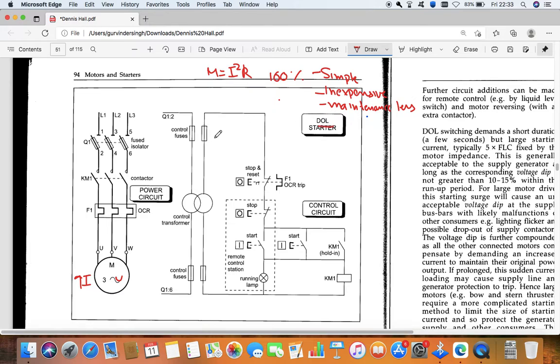Now I will explain the DOL starter. In any starter there are two circuits. One is known as the power circuit, and the other is the control circuit. The power circuit normally has a high voltage, which is the voltage going to the motor. Let us consider that voltage is 440 volt. But the control circuit has a reduced voltage, which may be 110 volt or 220 volt. Up to this is the power circuit, and this one is the control circuit.